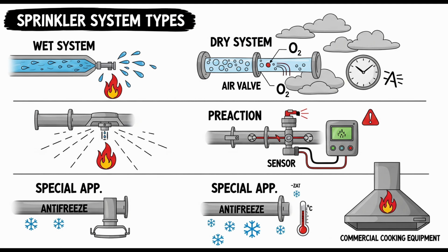So, this tiny hole allows the thermal expansion pressure of the antifreeze solution in that connecting piece of pipe between the supply valve and the check valve to push back ever so slightly against the supply pressure, bleeding off the expansion pressure, rather than letting that pressure build up in that small section and potentially damage the nearby sprinkler heads or fittings. That seems to be exactly the intent.